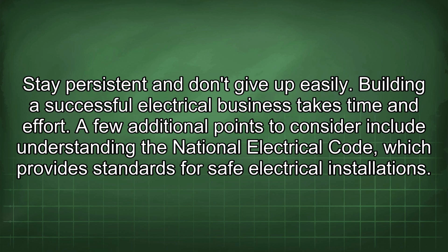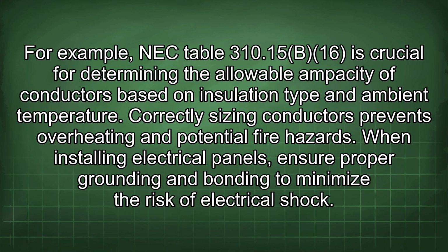A few additional points to consider include understanding the National Electrical Code, which provides standards for safe electrical installations. For example, NEC Table 310.15(B)(16) is crucial for determining the allowable ampacity of conductors based on insulation type and ambient temperature. Correctly sizing conductors prevents overheating and potential fire hazards. When installing electrical panels, ensure proper grounding and bonding to minimize the risk of electrical shock.